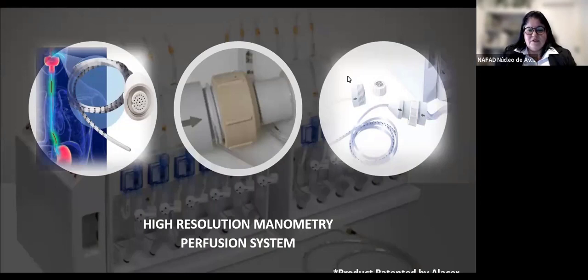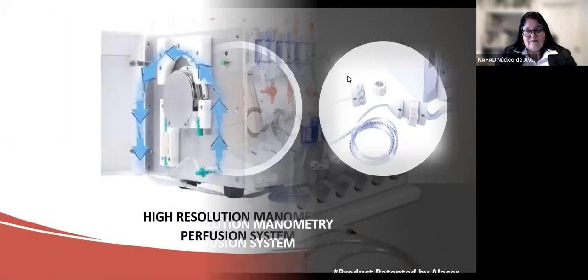Talking about technological evolution, since its emergence in the last century, water infusion manometry has undergone advances and the high resolution manometry device we work on today presents some very interesting details. One of them is the probes connection system to the device. The development of a single connector allows the rapid connection of the 36-channel probe with the high-resolution manometry device, which features a closed system with electronic sensors and stainless steel capillaries that produce a less compliant perfusion system.